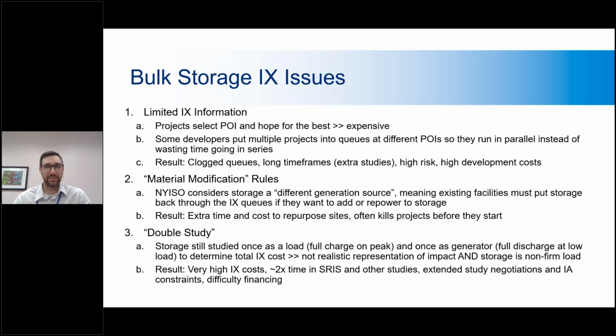Basically breaking the grid in two different ways during two different times that would never actually happen in reality, two separate study timeframes, and then adding those two interconnection costs together to determine the actual interconnection cost for that one project. Obviously, the result is extremely high interconnection costs. If you add a 100 megawatt battery charging on peak, there are going to be some system impacts. But the other issue is when running these two separate interconnection studies, the ISO often does them in series, which basically doubles the amount of time the storage interconnection study takes. Then, once you get to the end and realize you have these unrealistic operational assumptions and very high interconnection costs, only after your first study are you able to negotiate with the ISO for more realistic assumptions to mitigate those high costs.